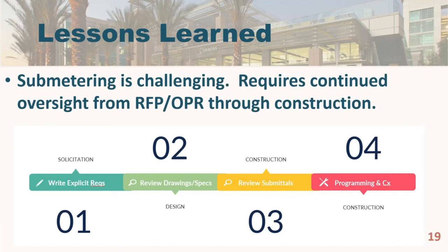As Susan mentioned, a lot of the lessons we've learned have made it into the county's RFPs. Writing explicit requirements is critical from the beginning. Reviewing the drawings and specs the whole way through to make sure the meters have the proper specification and communication protocol. All of the county's meters feed into their building automation system, so they need to speak the correct protocol. Making sure everything's interconnected, with conduit where it's needed. And then at the end, commissioning — making sure the meters are installed properly, reading properly, and programmed properly.